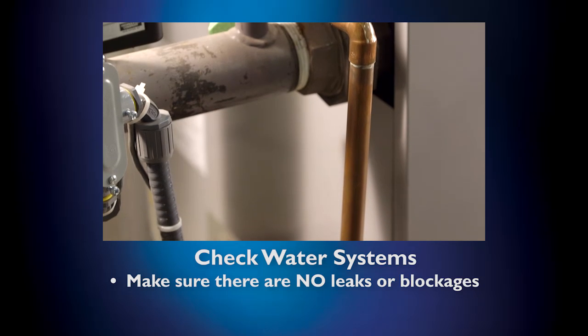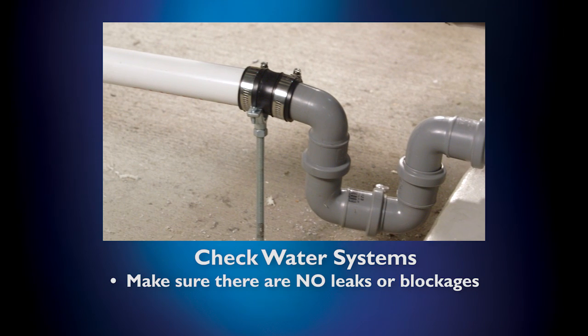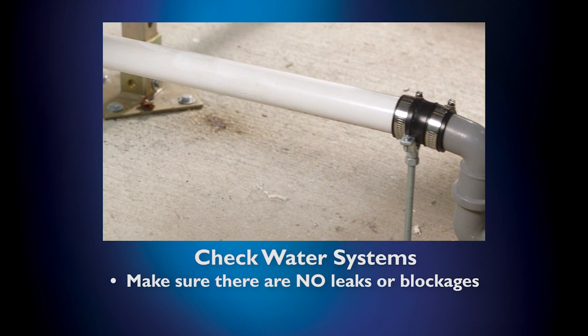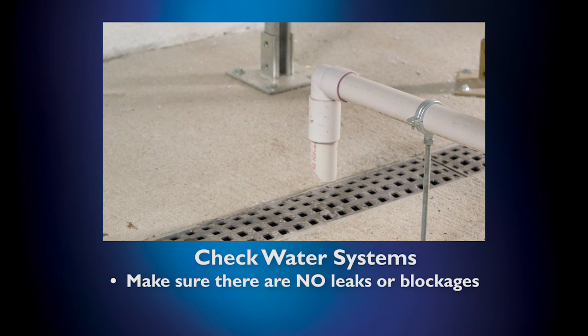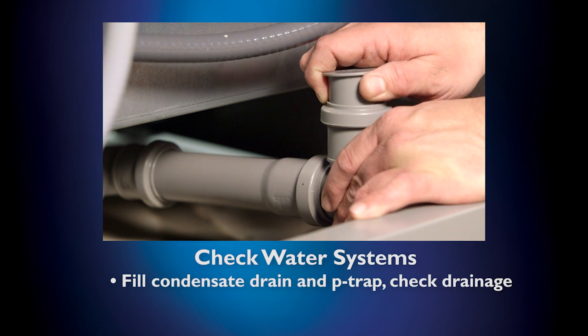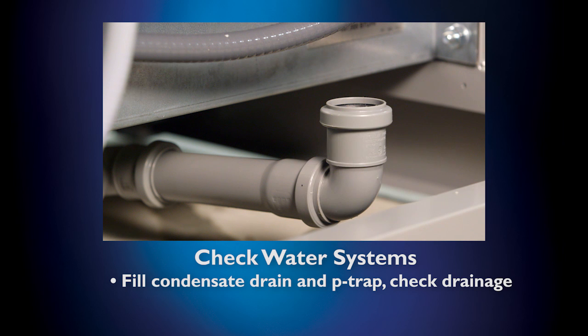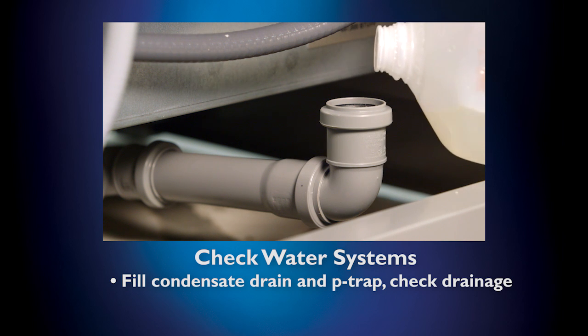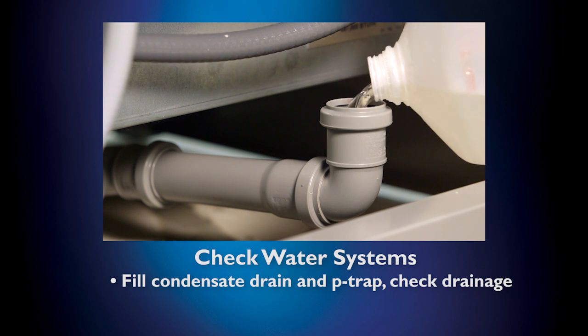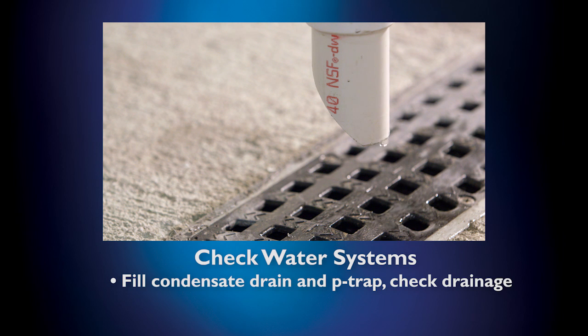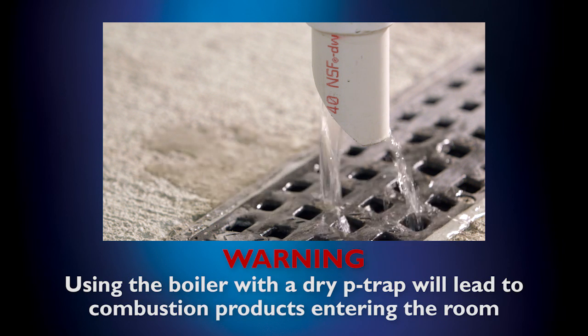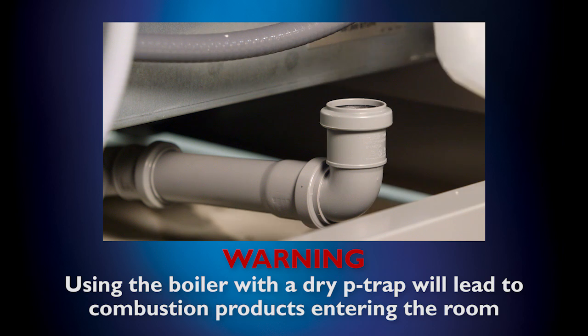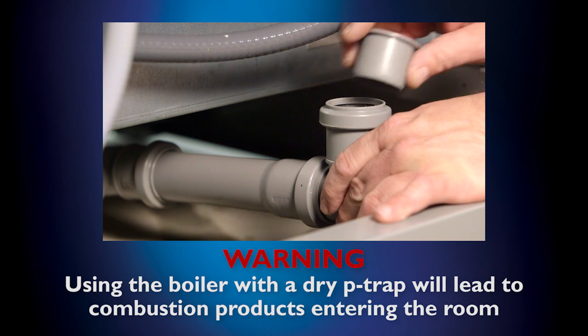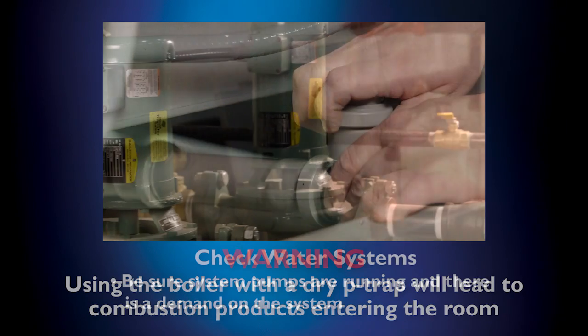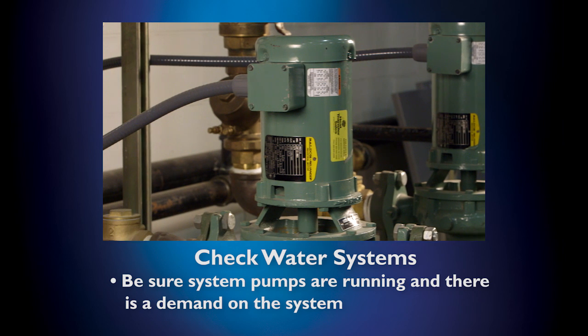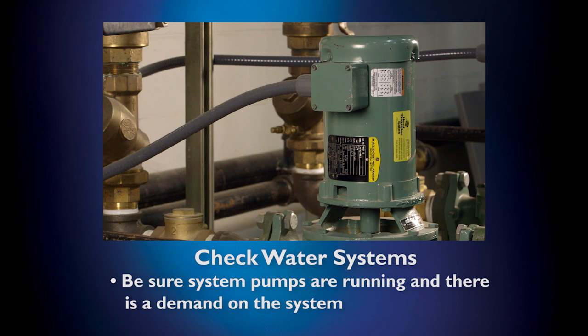Finally, check your unit's water systems. This means, check to make sure there are no water leaks or blockages to the wastewater system. The condensate drain and P-trap must be filled with water and connected to the wastewater system. You can do this by filling the trap with water through this hole and then check the correct drainage of the condensate. Using the boiler with an empty drain trap could cause a dangerous condition due to poisonous emissions from the flue exhaust gases. Finally, be sure that the system pumps are running and there is a way for the loop to dissipate heat.